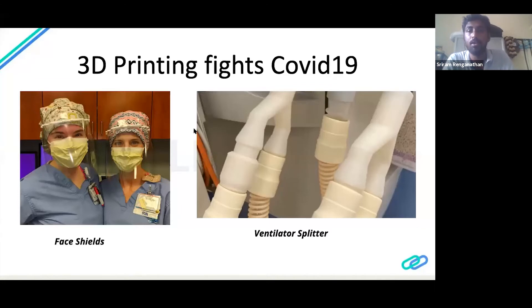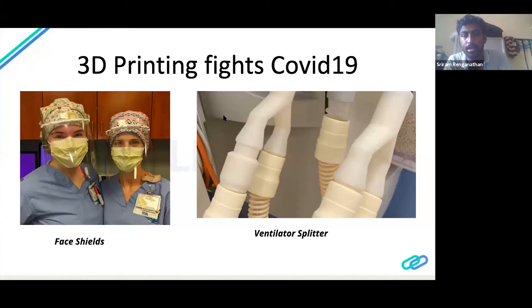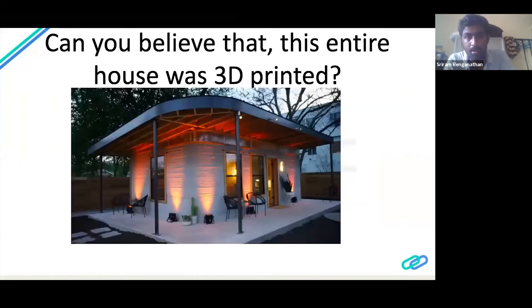A ventilator splitter is a very important life-saving device. India as a country has only 80,000 ventilators, but once the corona outbreak escalates we might need somewhere around five to six lakh ventilators. 3D printing has come up with a dynamic solution — splitting a single ventilator across two or three patients. The Y-junction you see is a ventilator splitter which splits oxygen to two patients, so one ventilator can serve two to four patients.